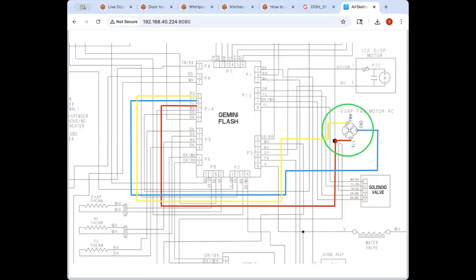So he's a newer tech and he's just getting still getting used to the process. And you know how they tell pilots when you're getting instrument rated, you got to trust your instruments. Same with us with techs, we got to trust our instruments. We got to trust our voltage readings and we got to trust our troubleshooting process. So if you got good inputs to something like a fan and the fan's not working, your mental troubleshooting algorithm is slam dunk bad fan motor.